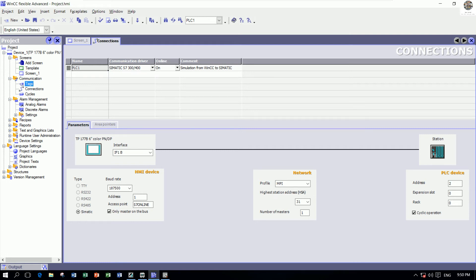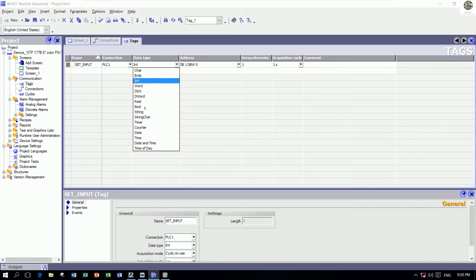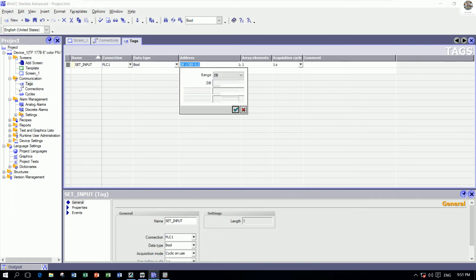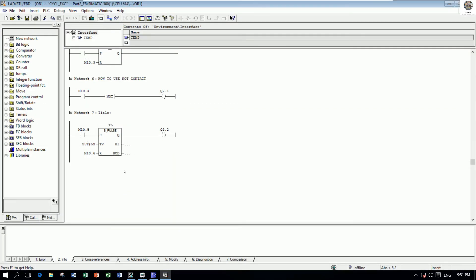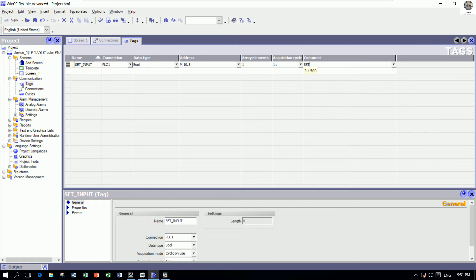Go to Tags and double-click on Tags. We can name it 'Set Input'. PLC1 is the connection we already created. The data type is Boolean because it will be true/false or on/off. The address is M10.5 — so I choose M, M10, and bit number 5. We can comment it 'Set Input Number 1'.